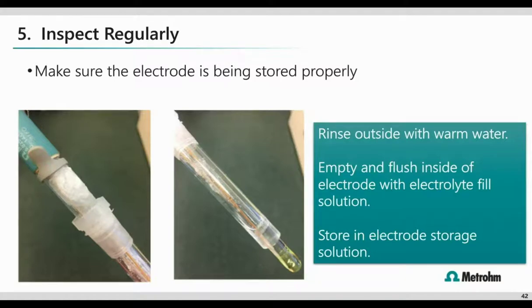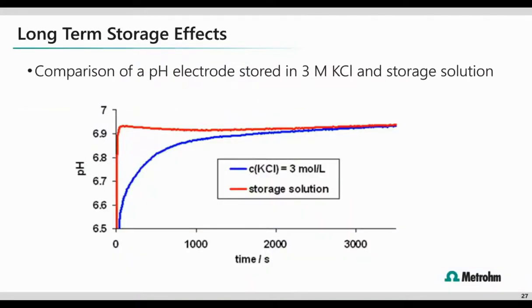Excellent, thank you. Now, can you explain again why storing the electrode in potassium chloride solution is not okay? Sure. So that slide, I think if I bump out to it, it would be really helpful here. So here, it's not necessarily storing it in the KCl. We're talking about long-term storage. This is a scenario when the electrode has been kept overnight in a KCl solution. The reason we don't want to do this is because those potassium ions will take up space in the membrane of the electrode. In order for us to be up and running quickly, we've got to get those flushed out. We need the hydrogen ions to be moving back and forth across that membrane, and if the potassium is in the way, we're not going to get a very accurate measurement. So that's the reason we really avoid keeping the electrodes stored in that KCl solution.